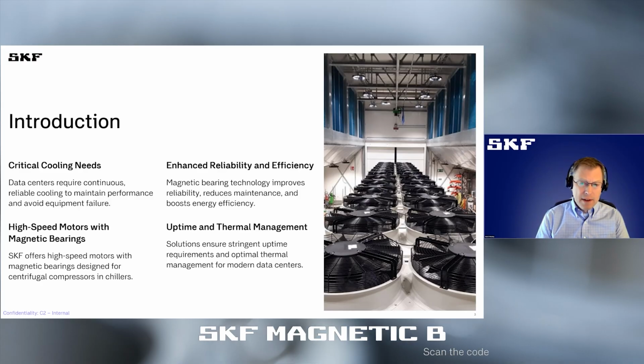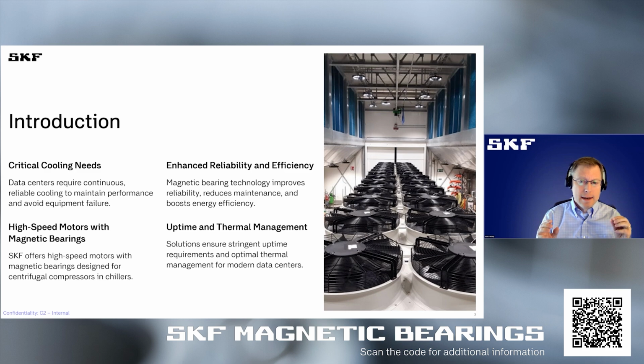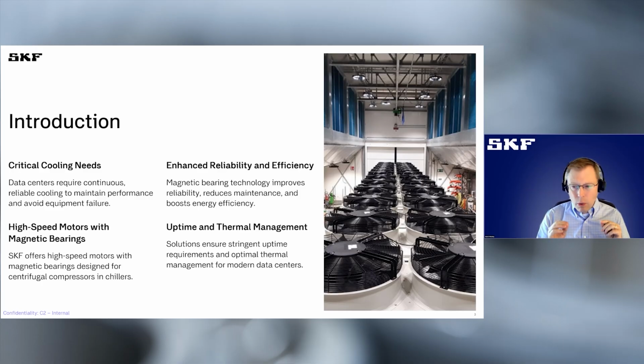This is where SKF's high-speed motors with magnetic bearings really shine. They're specifically designed for use in centrifugal compressors for both air and water-cooled chillers. A chiller equipped with this technology will have the highest levels of performance, engineered to enhance operational reliability, reduce maintenance requirements, and improve overall energy efficiency. As we go through the next few slides, I'll show you why these chillers, using this SKF technology, deliver less downtime, class-leading energy efficiency, and minimal maintenance requirements.